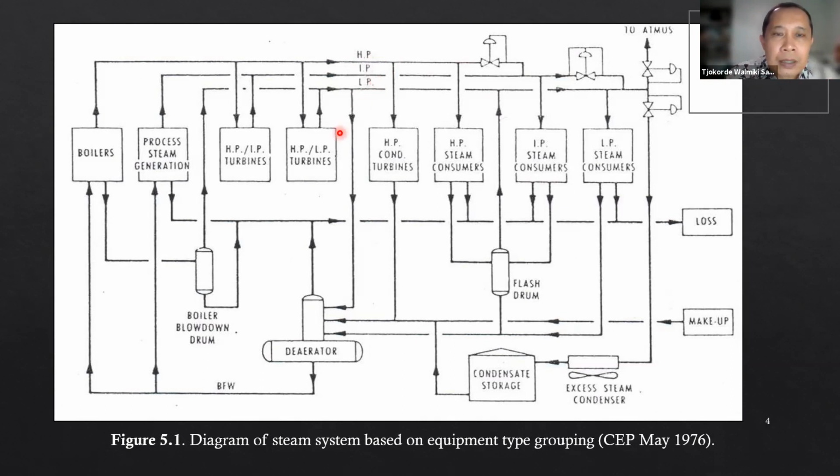Oke. Jadi yang terjadi di dalam turbin back pressure ini adalah mereka mengambil steam dari high pressure header, kemudian steam yang keluar dari turbin-turbin ini dikembalikan lagi ke header. Tetapi tentunya tidak bisa dikembalikan ke high pressure lagi. Dikembalikannya bisa ke medium pressure header atau ke low pressure header, tergantung dari bagaimana spek kerja turbin ini.